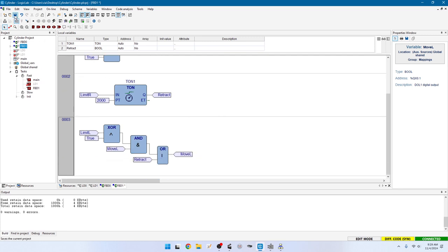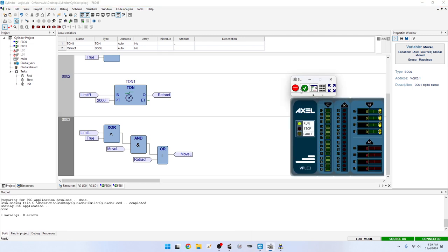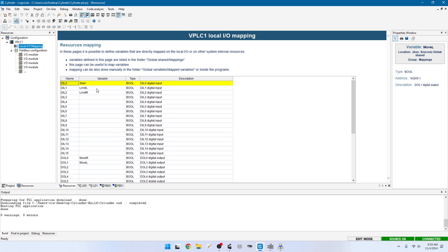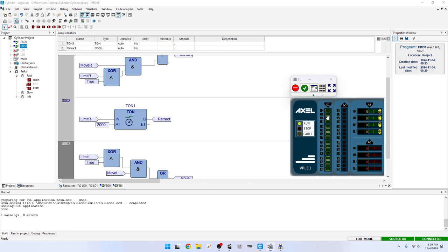Next, when limit right is true, we start a countdown TON timer named tOn1 with 2,000 milliseconds. The output triggers the retract variable. Then we implement: move left equals retract OR (move left AND NOT limit L). Add NOT limit L using XOR with true, AND with move left, and OR with retract. Output is move left. Save, F7 — no errors. F5 and run: start moving right, lose contact with left limit switch, hit right limit switch, wait two seconds, start moving left, lose contact with right limit switch, hit left limit switch, stop, ready to start again.